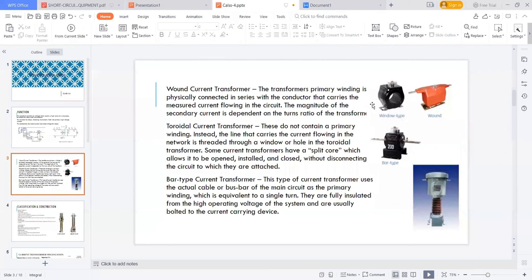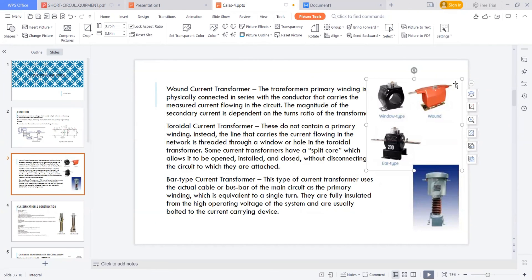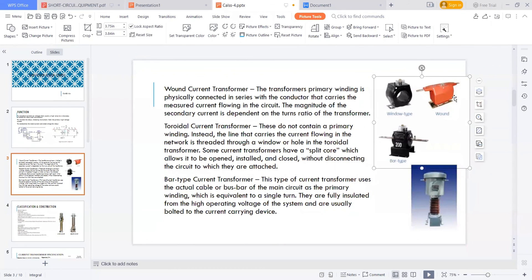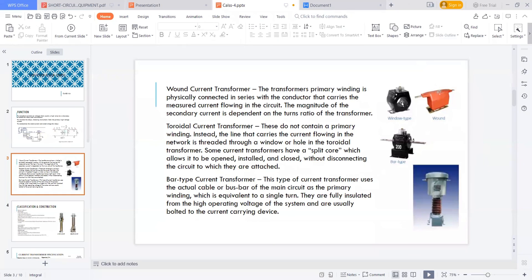For wound transformers, the primary winding is physically connected in series with the conductor carrying the current being measured. The magnitude of the secondary current depends on the turns ratio of the transformer. The window transformer — also called a toroidal transformer — works differently: the primary conductor bar is inserted through it. There is no separate primary winding; the conductor itself acts as the primary, and the secondary current is calculated from that.